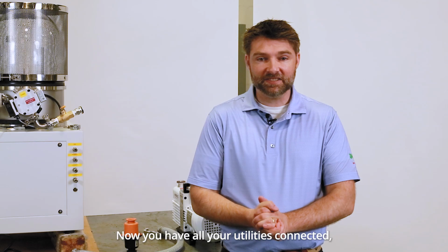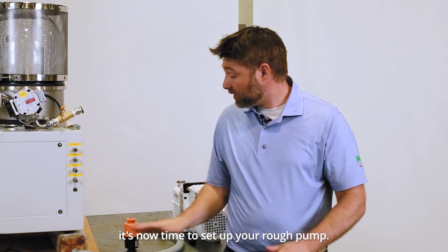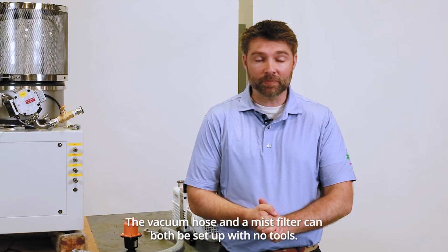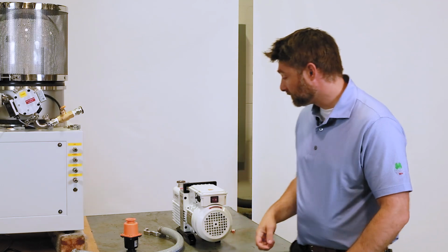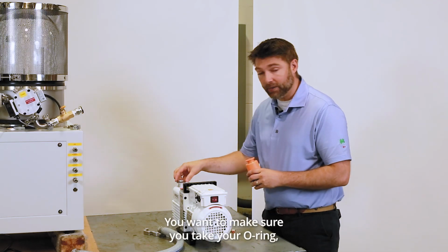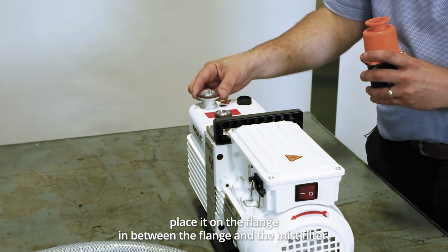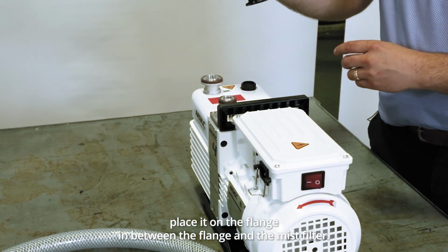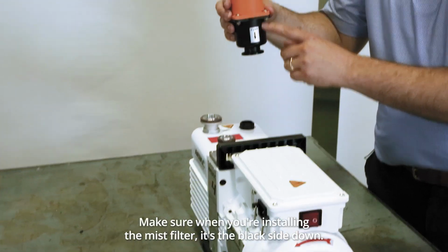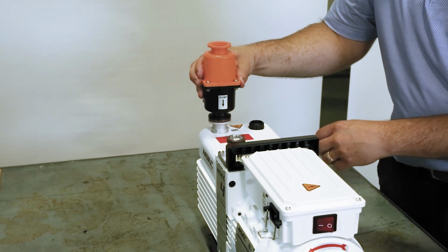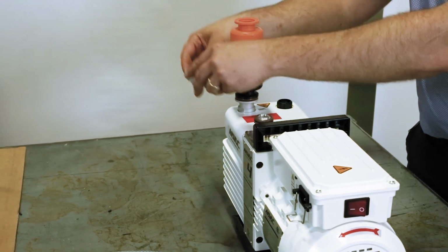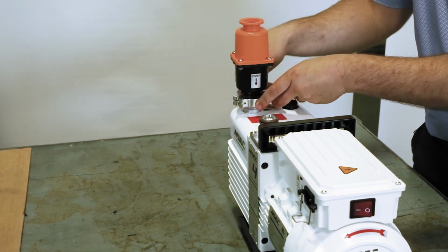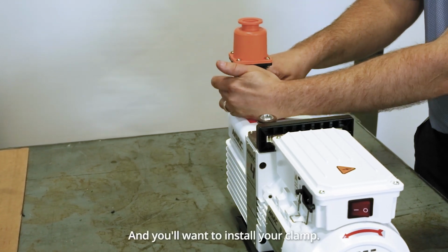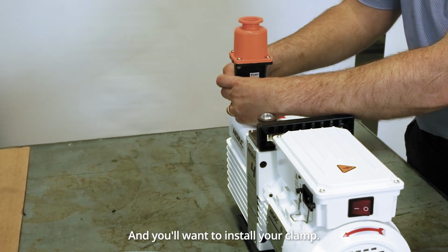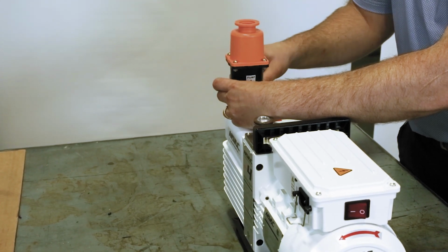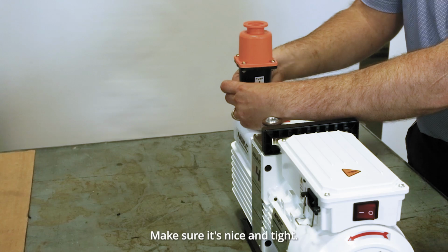Now you have all your utilities connected, it's time to set up your rough pump. The vacuum hose and the mist filter can both be set up with no tools. First, the mist filter: take your O-ring and place it on the flange, in between the flange and the mist filter. Make sure when you're installing the mist filter, it's the black side down. And you want to install your clamp. There you go. Make sure it's nice and tight.